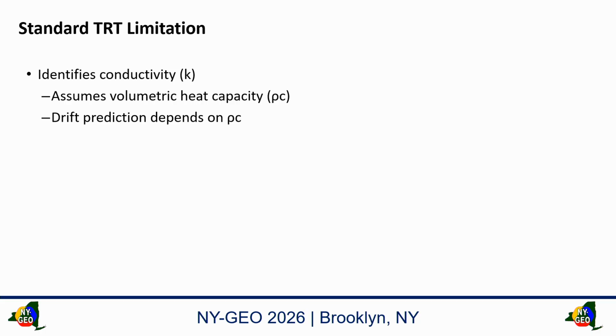So when you have a borehole, or a whole ground heat exchanger down there, mostly vertical, you do a normal thermal response test and look at the radial heat flow going out. That's all you're looking at. But these systems have space and time. I've got a borehole with a cylinder around it that's changing in temperature as it goes further out, radially, so it gets bigger. Now I've got a space and time constraint I have to think about radially.